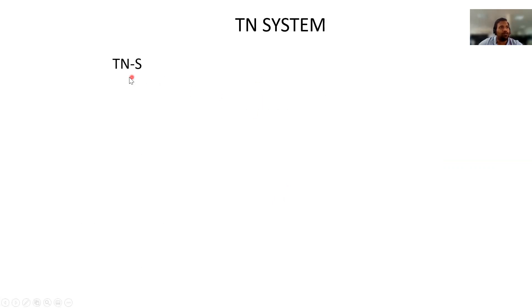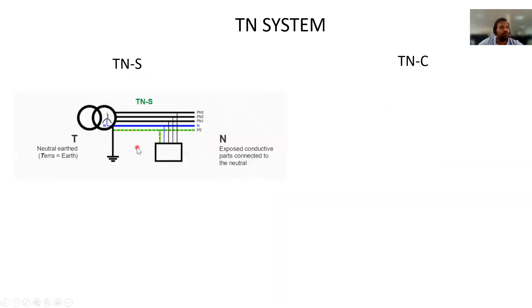The TN system has two classifications: TNS and TNC. In the TNS system, the supply-side neutral is earthed and a separate earth conductor runs from the supply end all the way to the load end, directly connecting to the equipment. Since the earth and neutral are separated, this is called TNS — T for earth, N for neutral, S for separated.